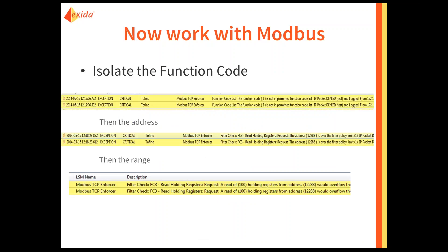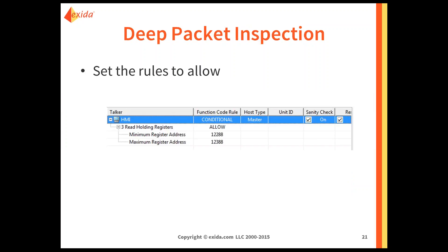Once we send it to the enforcer module, we have to account for the same information as we did for the Moxa. The first thing we need to know is the function code. Then we need to know what addresses are being accessed by that function code, and how many of them. The Tofino will give you all this information as you step through. You should know it in advance — you should know what your control system is trying to do. The devices you're putting on the network can help you get there, but that's no replacement for knowing the functionality of your system. So we go into the deep packet inspection or enforcer module of the Tofino, specify the HMI as the communicating device, select function code 3, tell it the registers it's allowed to communicate with, and it's up and running.